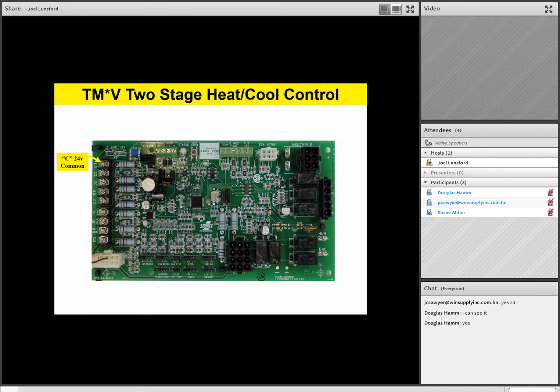G is our 24 volt input from the furnace, or excuse me, from the thermostat, for G, our fan call. R is 24 volt hot. W1 is going to be our first stage heating call. You'll notice it's also silk screened W/W1, because if you're stuck with a single stage thermostat, even on this great two-stage heat, two-stage cool, variable speed control board, if you're stuck with a single stage heating thermostat, we can still give you some staging function with a staging jumper, which we'll talk about in a little bit. Y2 is our second stage cooling call. Y1 is our first stage cooling call. And W2, just like before, is our second stage heating call.